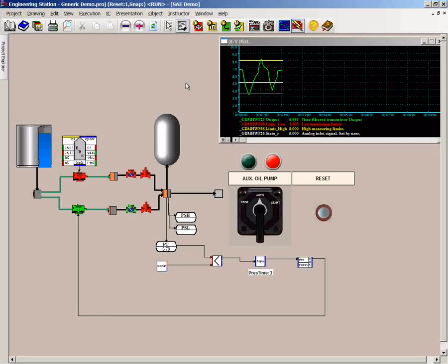Now, with the system reset and stabilized, and only this change in here, we run the scenario again, stopping the running pump, and now we'll see that we no longer meet design criteria because the pressure degrades much faster, as we expect. Several possible design changes may be made to mitigate this problem.